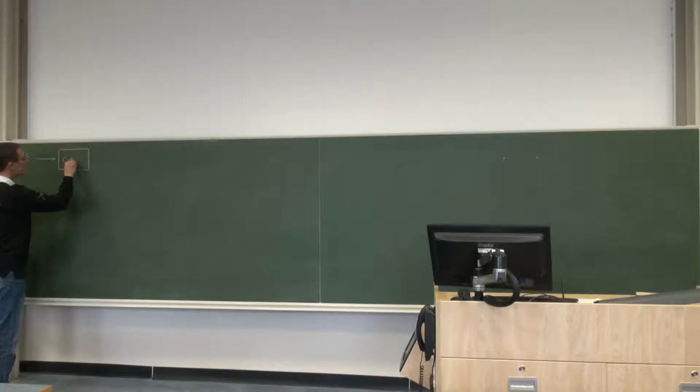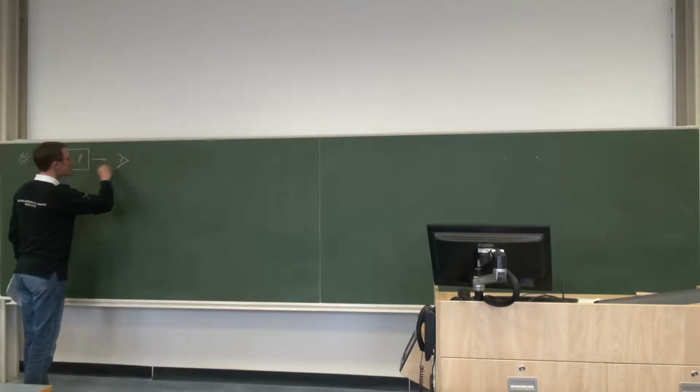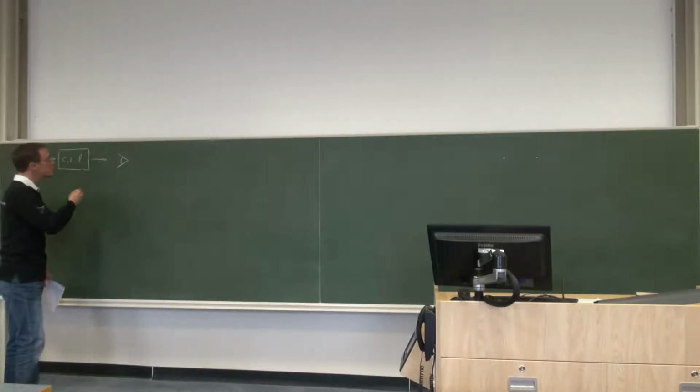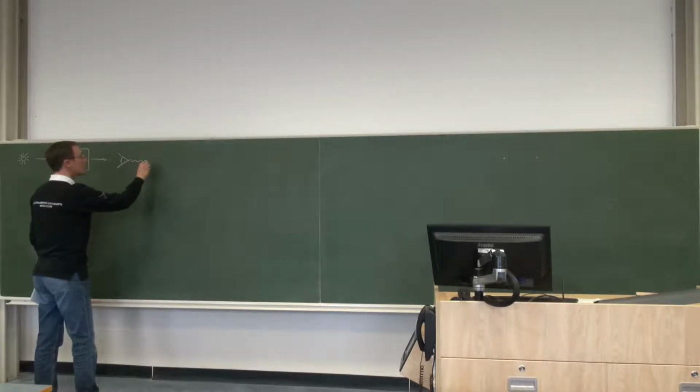Each substance is unique in how strongly it absorbs light, so it has something called the extinction coefficient. And then, of course, the longer the cuvette, the more light is going to be absorbed in it, so the length of the cuvette also matters. The light that exits the cuvette flies into a detector that perceives the intensity, compares it to the original intensity, digitizes it, and on it goes into a computer for processing.